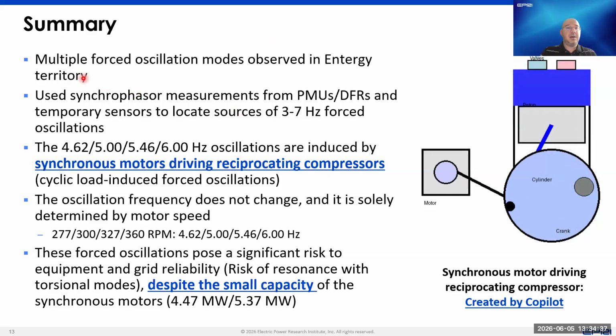So to summarize, the motivation for this analysis was multiple forced oscillation modes that were observed in Entergy's grid territory, in different areas. We used PMU data from Entergy's PMUs, but also from additional temporary sensors that were deployed during the project to locate the source. We were successful in identifying that the source of those oscillations was synchronous motors driving reciprocating compressors. The frequency of those oscillations correlates with the speed, the RPM, of the motors. You see here the correspondence between the RPM and the frequency.